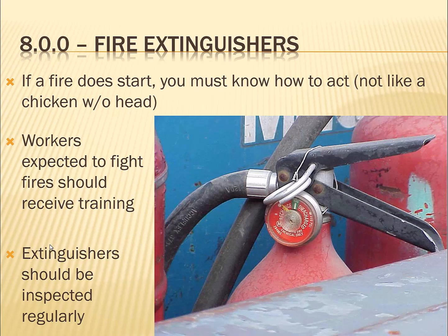You shouldn't need wire clippers to cut the thing in order to use it. Well, this thing's probably spent anyway, so it wouldn't matter. So fire extinguishers should be inspected regularly. You pick them up to make sure they weigh the right amount, check the pressure, but they actually have to be officially inspected by a qualified person once per year.